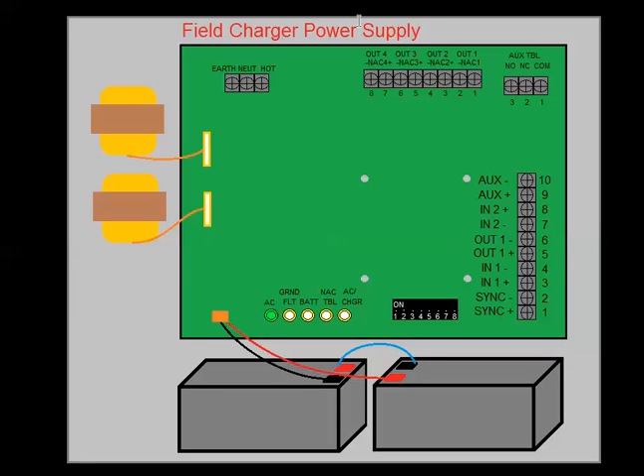Sometimes they'll have these things continuously powered up and use them for power, like to power door holders or something like that. If it's continuous use power, you have I think two amps less. So if you have the six amp model, you only can use four amps of it continuously. And if you have the eight amp model, you can only use six amps of it.